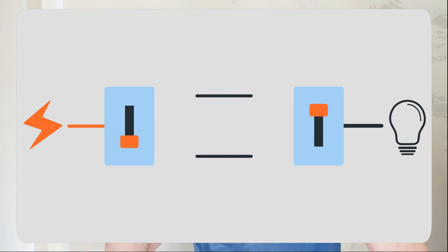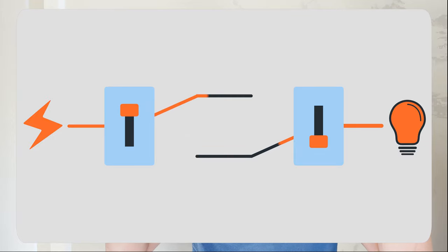The basic idea is that you are choosing between your two lines, and the two three-way switches on both sides basically just decide, hey, are we going to be providing power on this line? If both of them are connected to this top line, then great, you get power through that way. If they're both connected to the bottom line, the power goes that way. And if they're switched, then nothing flows at all. And that is really it. It's getting that power from the first box to the second box, and then if there's power between those two, it goes up to the light just like normal.